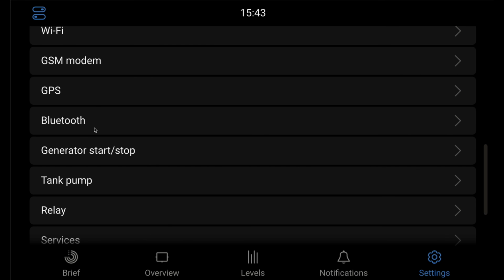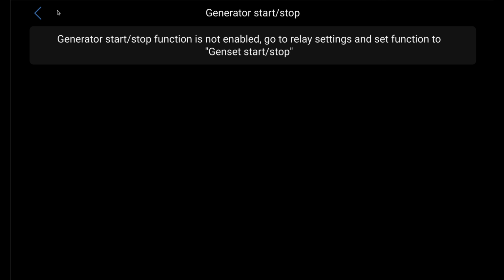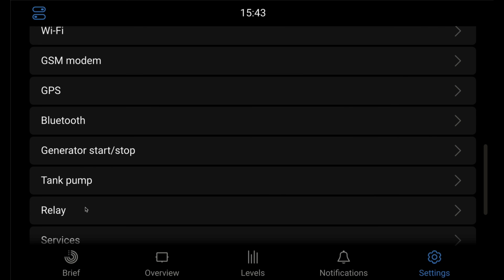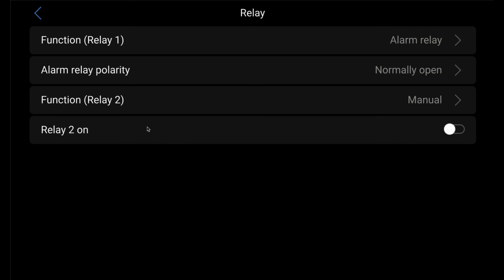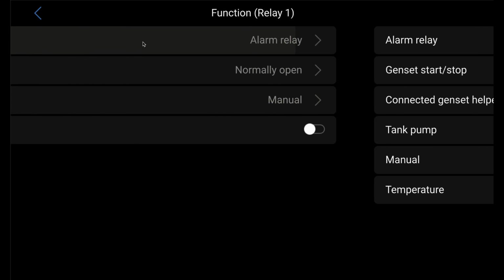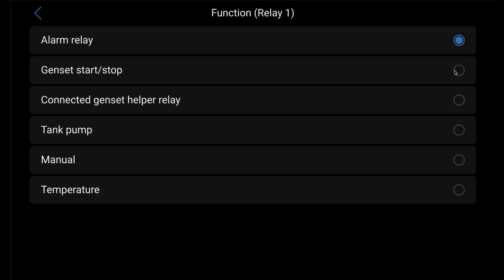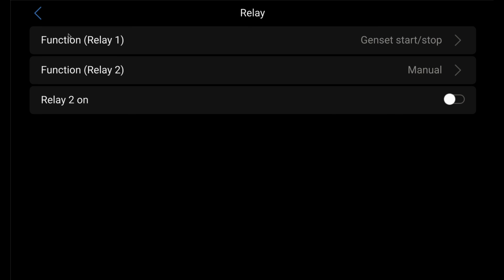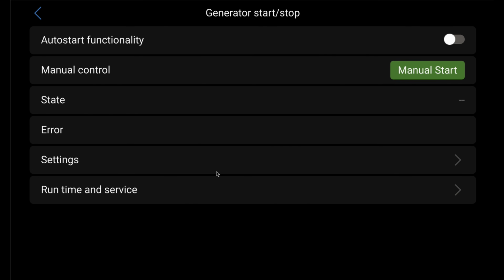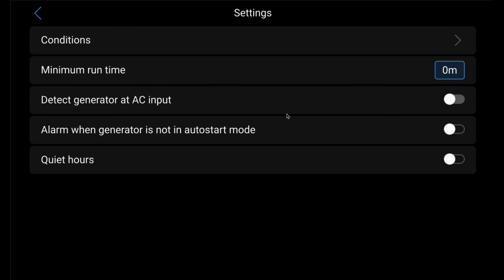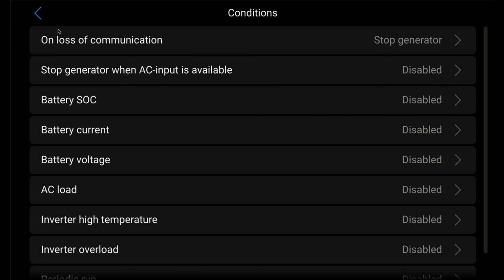Below the Bluetooth here, you can see we have a generator start-stop tab and a tank pump tab. When we click on these initially, you can see that they're disabled. But going here into the relay tab, we have the option of setting or defining the function of relay number 1. If we define relay number 1 as a gen start stop and we back out of here, we'll now have options available under this generator start stop tab to program start-stop conditions for our generator, or when relay number 1 latches and unlatches.